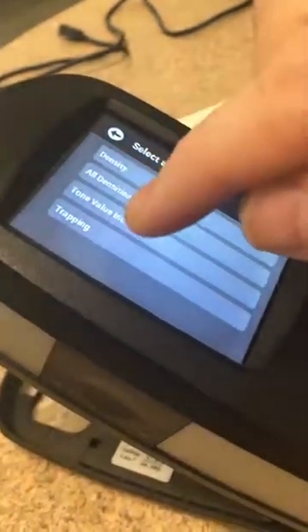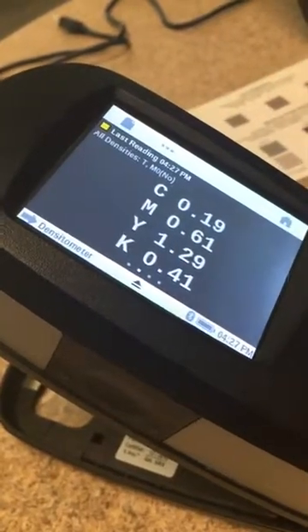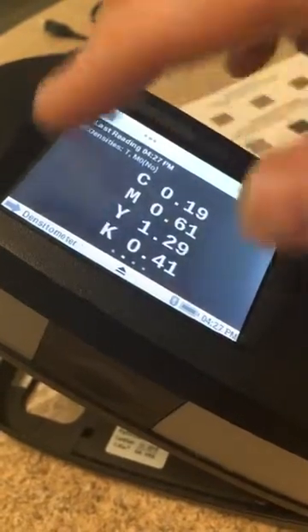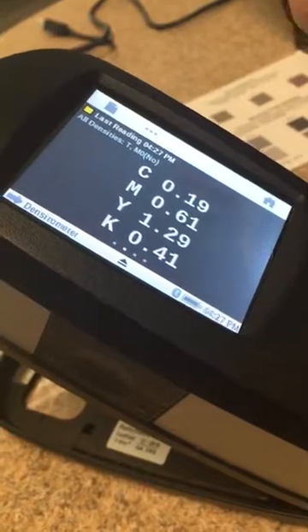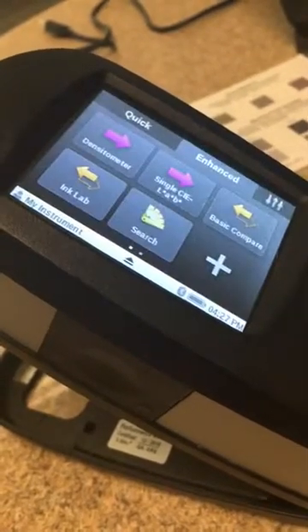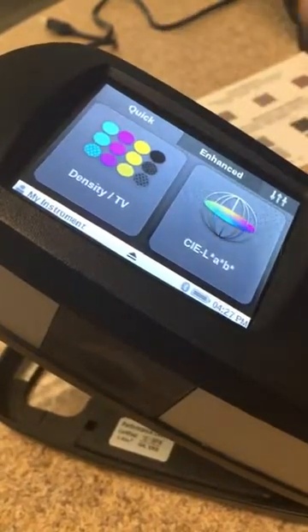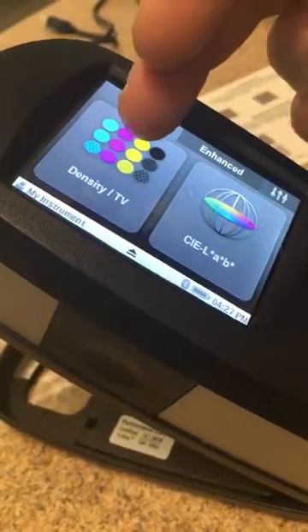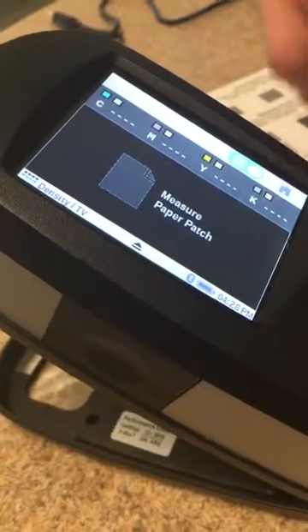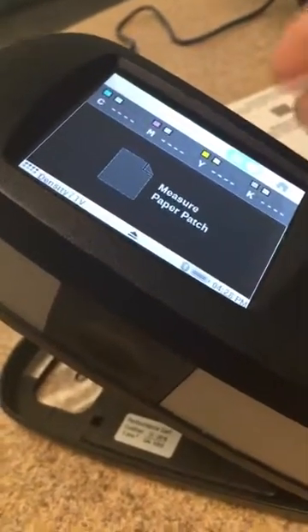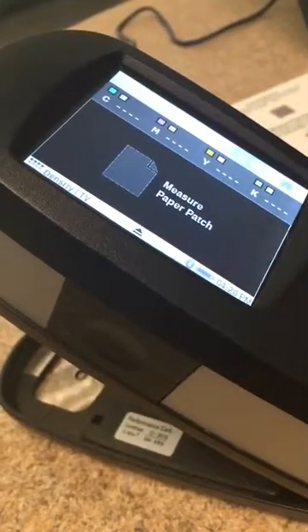All of these menu structures work very similarly. In the densitometer function, I can take a measurement and push the button to look at trapping if I have it turned on, or look at all density values for a particular color — like all the density values for that orange I measured. Once you learn one menu structure, you've learned them all. In the quick mode at startup, there are two main icons: one for a LAB measurement and one for straight density measurement, letting you quickly measure black, cyan, magenta, or yellow and store those numbers for easy reference.